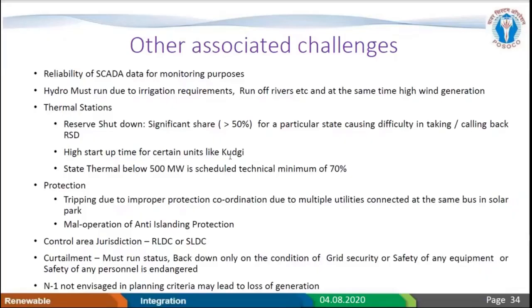Protection is another challenge. These generators come in at 33 kV to a pooling station, and protection coordination is difficult at their place. There have been trippings, and because of improper coordination, the 220 kV site gets tripped. Now we are taking this up and they have been installing fixes.